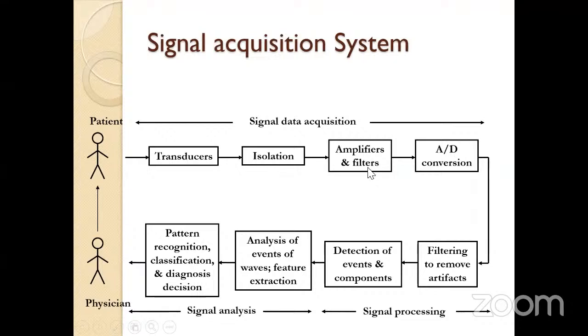When I say filters, for example, each of the signals, ECG, EMG, has a different frequency range. Based on our application, we need to filter out the required signals. These filters are circuits which allow only a particular bandwidth of frequencies. That is the function of filters. Then it is given to analog to digital conversion, wherein whatever signal we acquire will be in the form of an analog. When we say signals, these can be an analog type or a digital type.